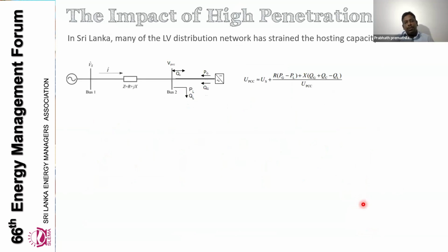So due to these high penetrations, what is the biggest challenge that we are having now? One of the biggest challenges is voltage. We know our LV distribution network is not designed to host solar PV systems. Normally in our distribution network, the LV line length is more than 1 kilometer. Likewise, our distribution network is not designed for this.